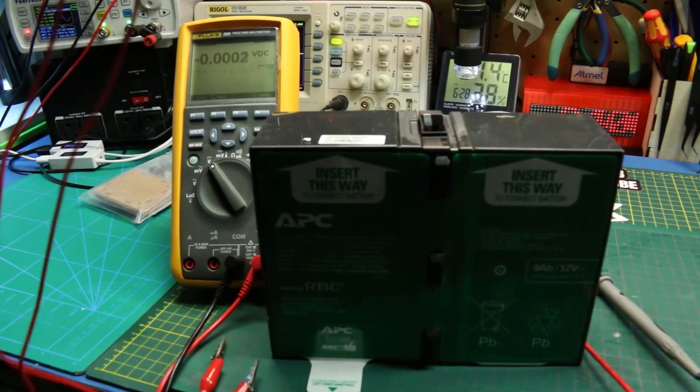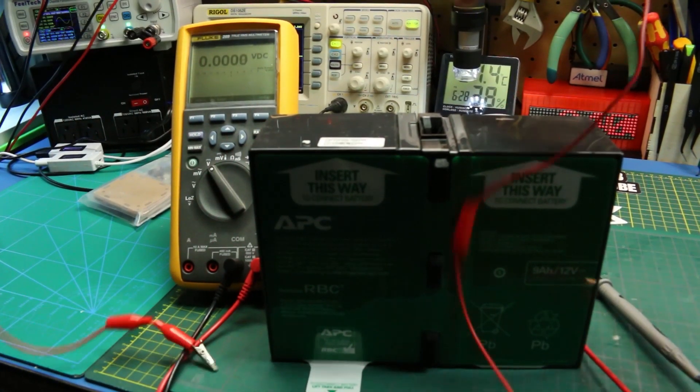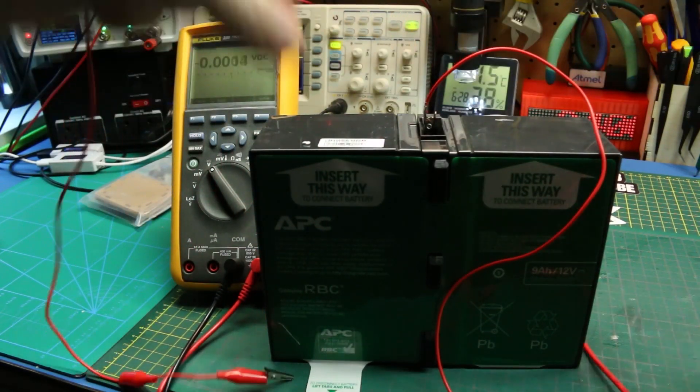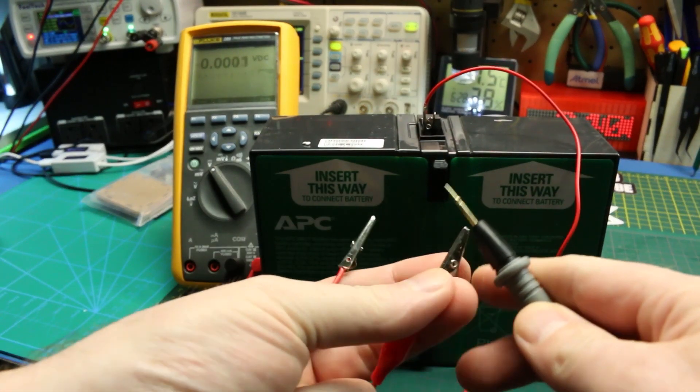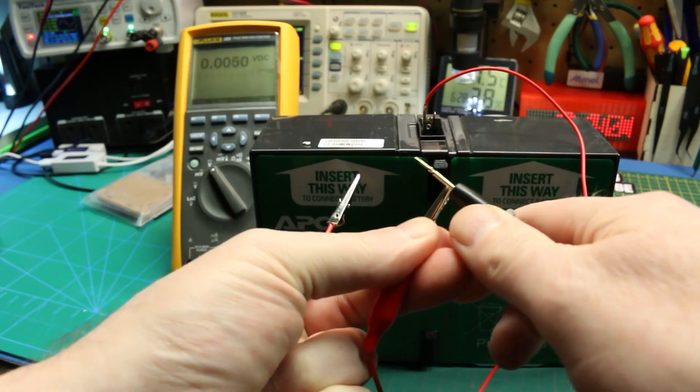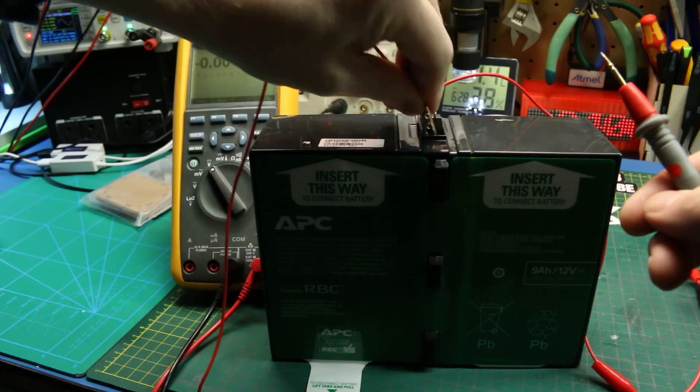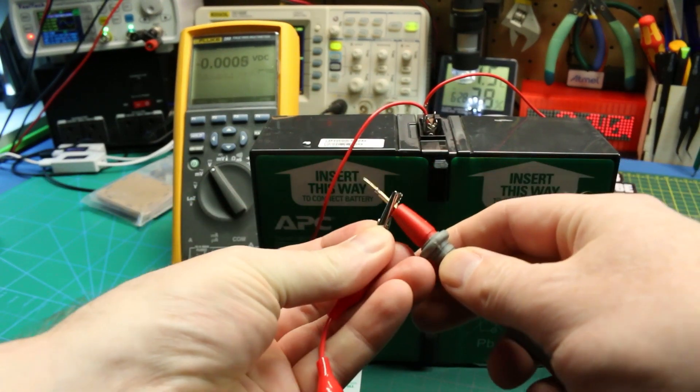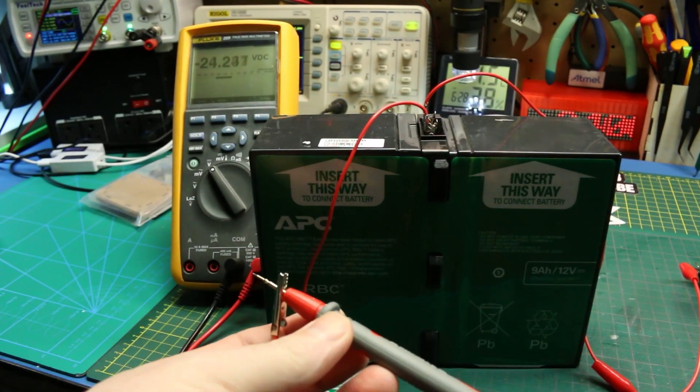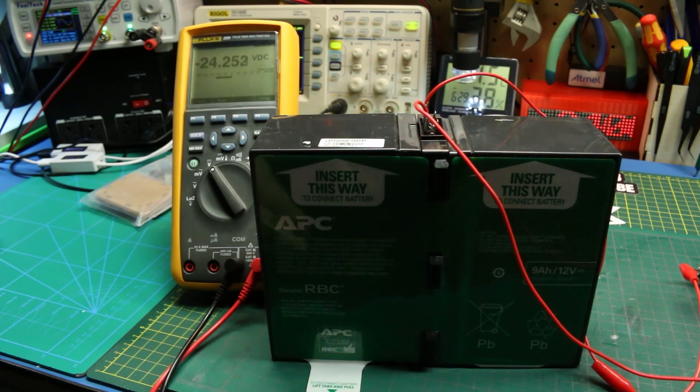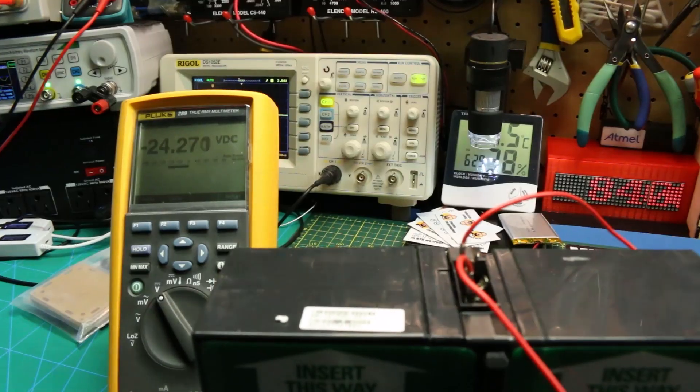When we have 24 volts like that, well that immediately makes me suspect that we have a capacity problem and we can test that. Not with just the meter. We need to do some rigging here, and the easiest thing to use is simply just an automotive bulb. Ideally you should use two automotive bulbs in series or find yourself a 24-volt bulb, but for short bursts like this just to load it down, the 12-volt bulb would be fine. They're pretty resilient, but if you blow it, so be it, just a bulb.